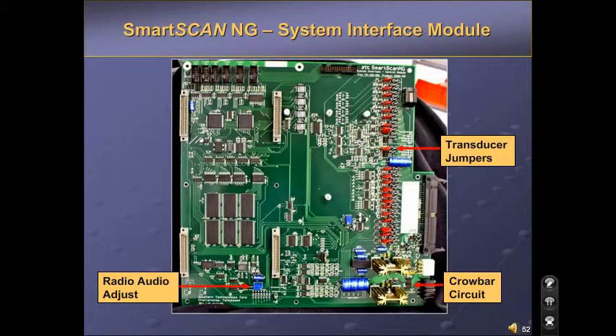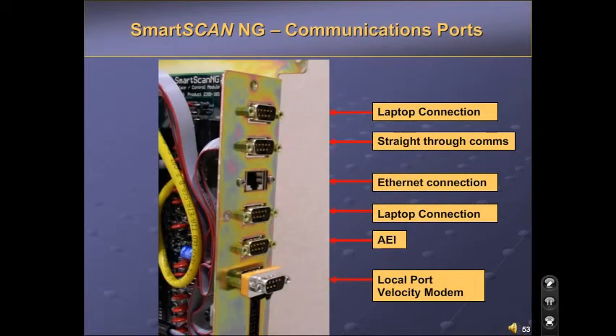The loading jumpers for the transducers are located on this board, J201 and J202. The loading resistors offer three levels: 100 ohms, 220 ohms, and 470 ohms. All units are shipped with the jumper in the 100 ohm position. Using the loading jumpers will be covered later in this presentation. The NG systems offer 6 COM ports. COM1 will be the most common for laptop use. The configuration of the remaining ports will depend on firmware.